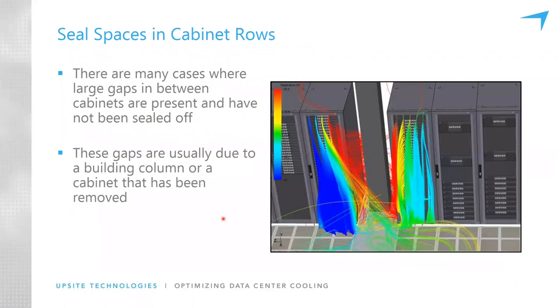Another important space to seal are those spaces in the rows where there's missing cabinets or gaps between cabinets. Again, CFD analysis is showing how hot air is flowing from the hot aisle through the space between the column and the cabinet and causing elevated temperatures just along the edge of the cabinet. You see this side of the cabinet is actually receiving nice cool intake air temperatures. This is a little warmer, but still much cooler than this edge. And these can vary. Sometimes the hot air will come in and fill and cause high temperatures across the whole top of the cabinet or some portion of the cabinet.